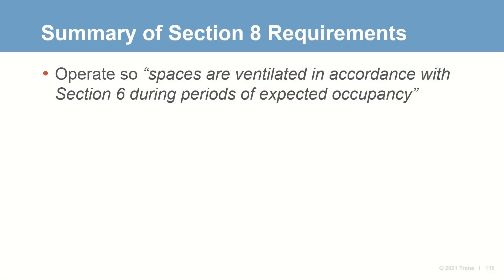Section 8 then addresses operation and maintenance. This section clarifies that the ventilation system must operate such that spaces are ventilated in accordance with Section 6 during periods of expected occupancy — so not necessarily 24 hours a day, just when the zone is expected to be occupied.